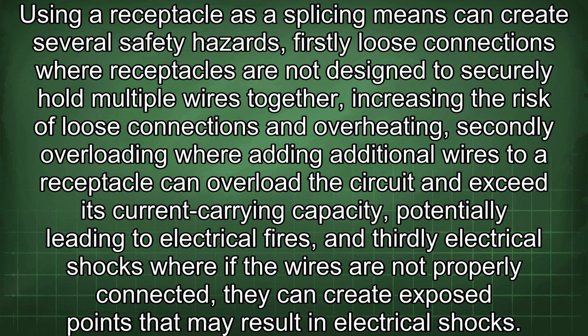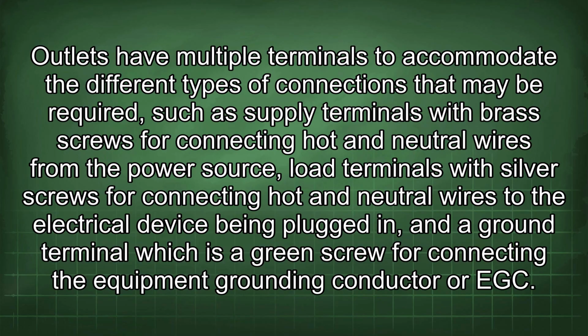in electrical shocks. Outlets have multiple terminals to accommodate the different types of connections that may be required, such as supply terminals with brass screws for connecting hot and neutral wires from the power source, load terminals with silver screws for connecting hot and neutral wires to the electrical device being plugged in, and a ground terminal, which is a green screw for connecting the equipment grounding conductor or EGC.